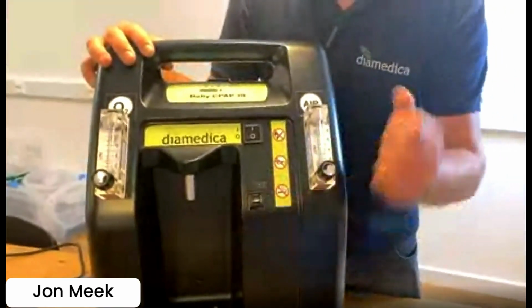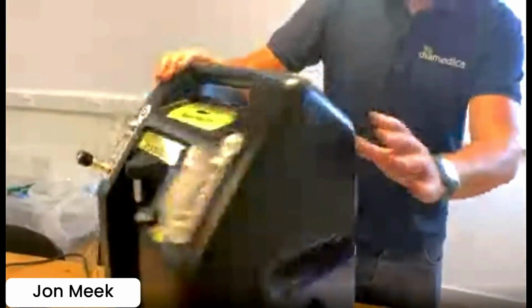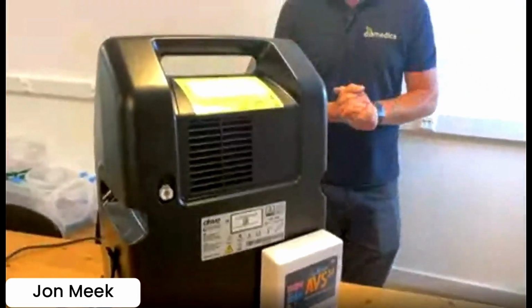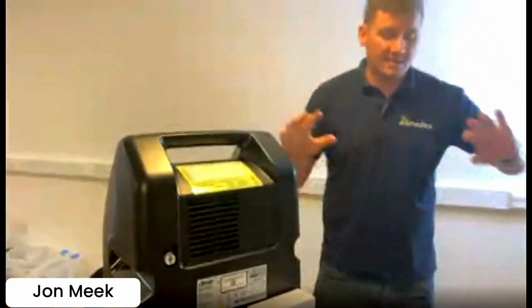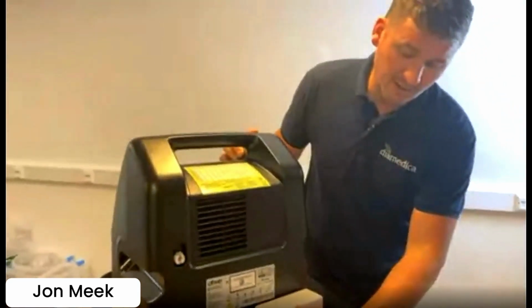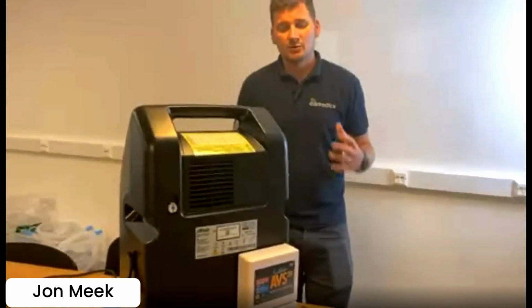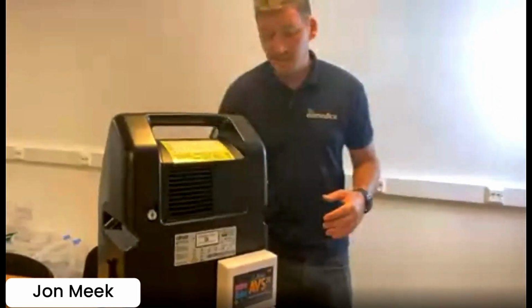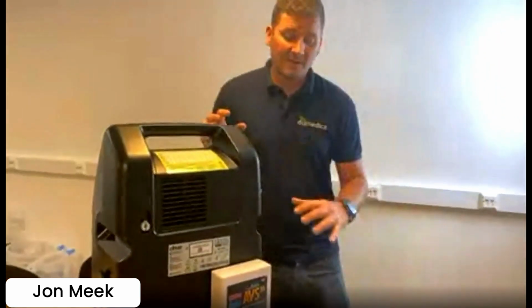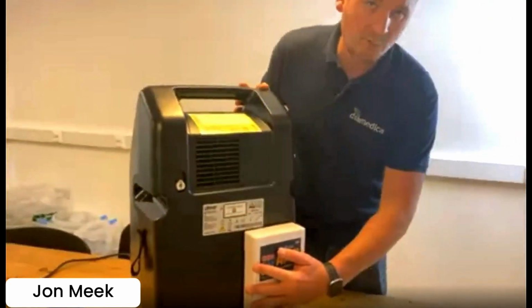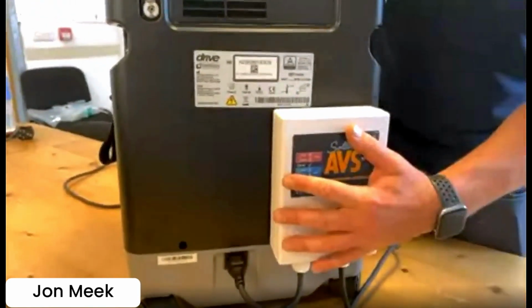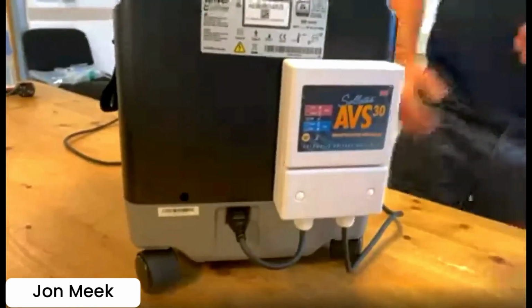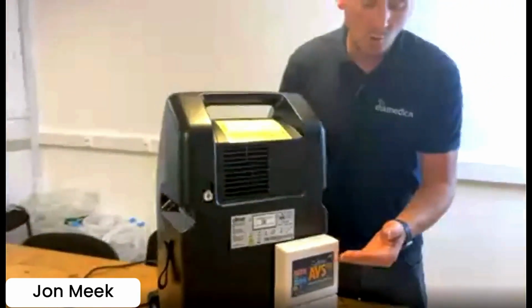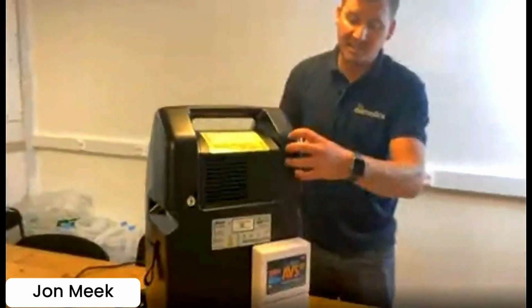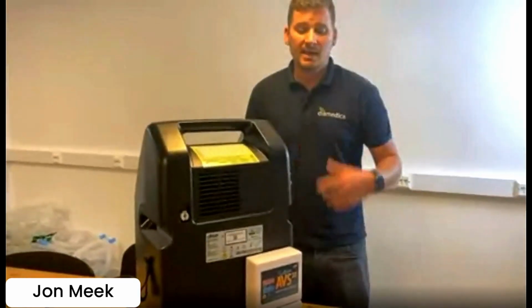So I've said that we have a circuit breaker. As we know, we sell and have worked in these areas for a long time. What this means is we have learned that power is one of the biggest issues we were struggling with on all our products, and as I've come across with many medical products. So on everything we have fit an external voltage protector. This provides voltage protection within a certain range. If it exceeds 250 volts or goes below 190 volts, which is the minimum this needs to run at, it will cut out.